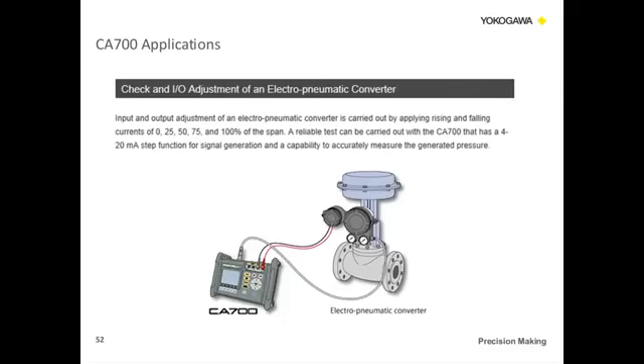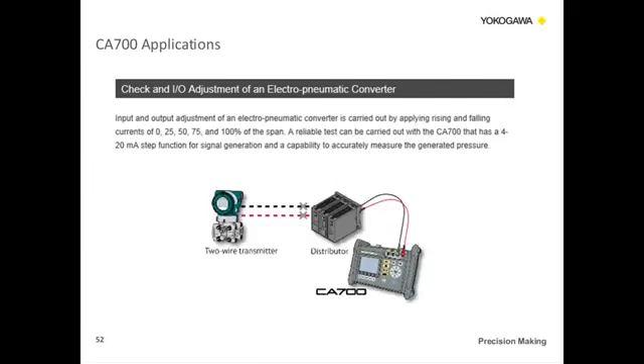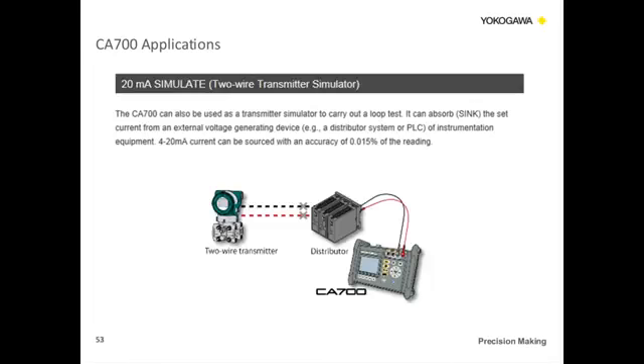Also, for checking input and output adjustment of an electropneumatic converter, adjustments can be done at 0, full scale, or 0, 25, 50, 75, as many points as you would like. We can take the actual pressure and the current measurements. There's also a sink function. We can do a 20 milliamp simulate like a 2-wire transmitter simulator. Having that sink function, we can act as a load in the loop and carry out this function also.